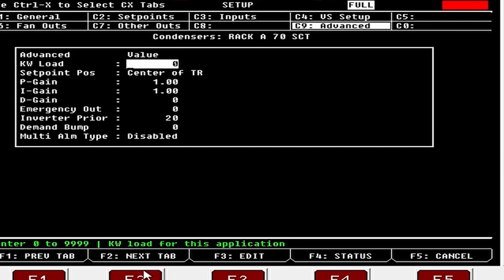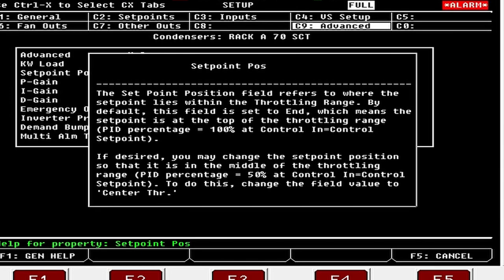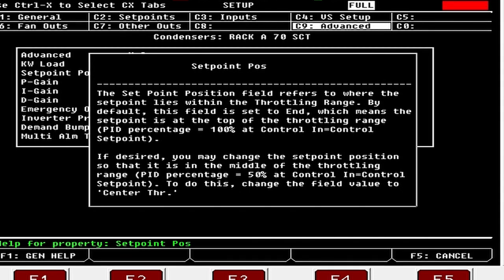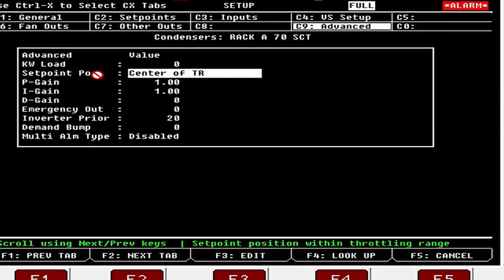The next tab is our Advanced tab. Set Point Position defaults to End, meaning the set point is at the top of the throttling range where PID percentage equals 100. I usually set it to Center of TR — the middle of the throttling range. By default, your P and I values are all set to one. We don't use the D gain on HVAC stuff; we're just doing a PI loop most of the time.